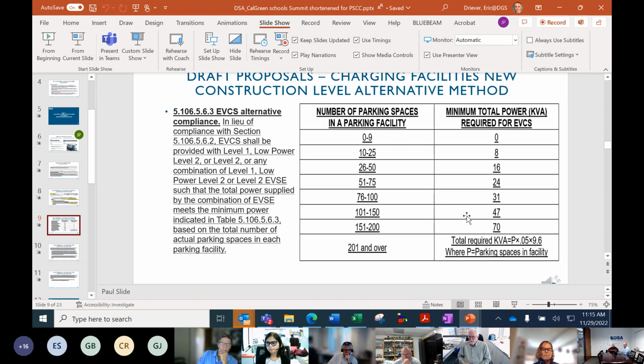On the right, for 0 to 9 spaces, 0 KVA is required. For 10 to 25 spaces, 8 KVA of charging is required to be installed. This charging can be met in a multitude of ways: level 1, level 2, low level 2, or level 2. You take the amount of KVA, which is the power supplied to the charger, and add that together.